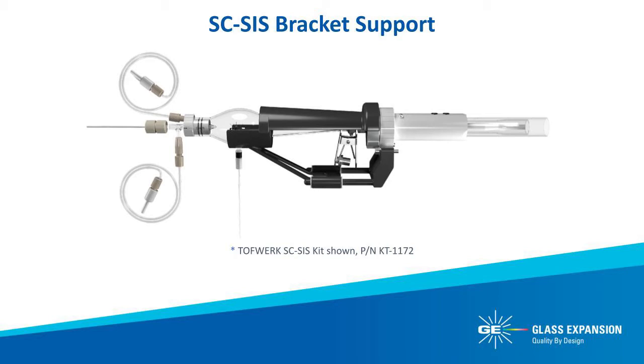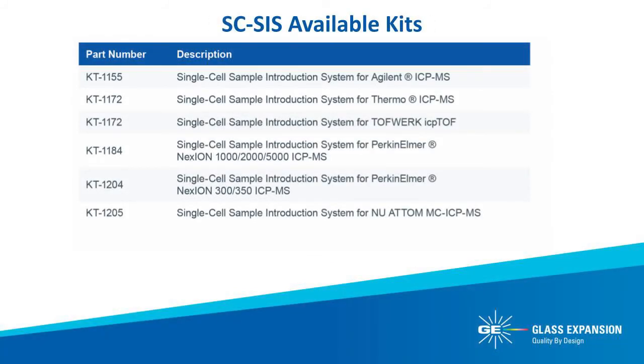Every Glass Expansion Single Cell Sample Introduction System kit is designed to suit a specific instrument model, which includes a mounting bracket support. Shown here is our complete kit for the TOFWERK ICP-TOF and the Thermo ICAP-Q/RQ/TQ quadrupole ICP-MS, Glass Expansion part number KT-1172. The system is currently compatible with all Agilent ICP-MS models, the Thermo Fisher Scientific ICAP-Q/RQ/TQ, the ICP-TOF from TOFWERK, the PerkinElmer NexION 1000, 2000, 5000 and NexION 300/350 series, and the new Attom Multi-Collector ICP-MS.